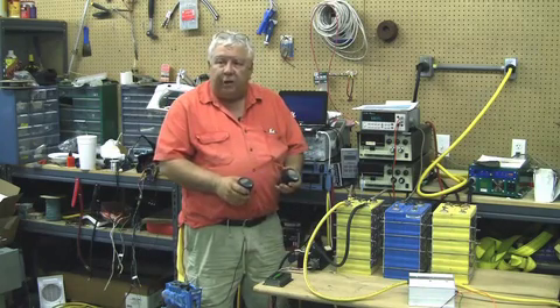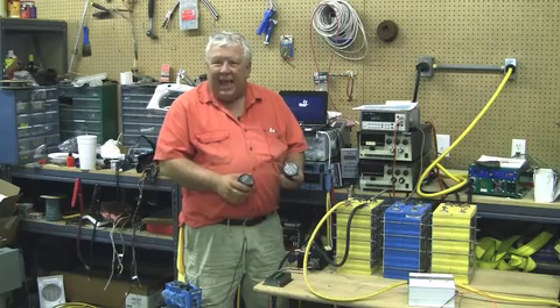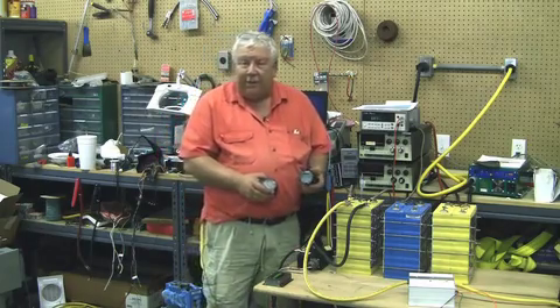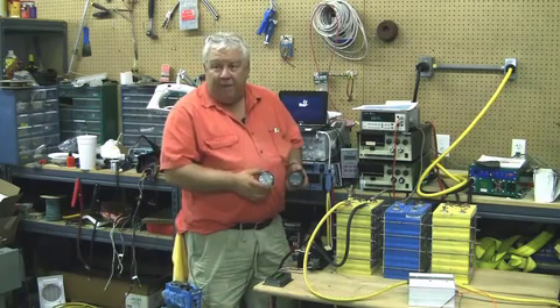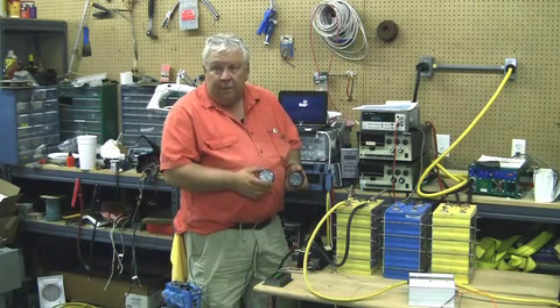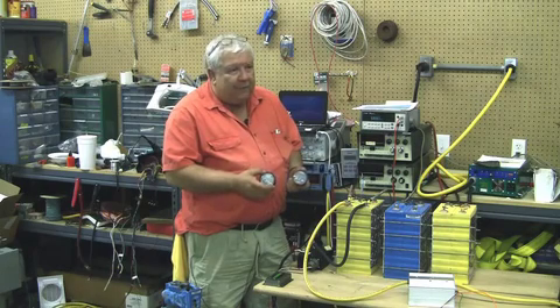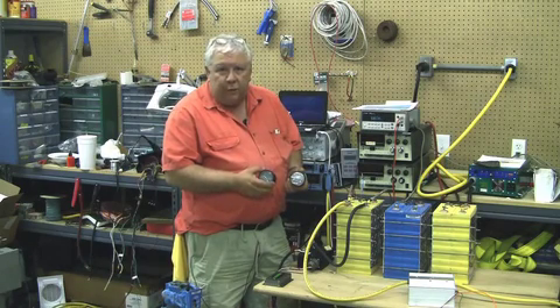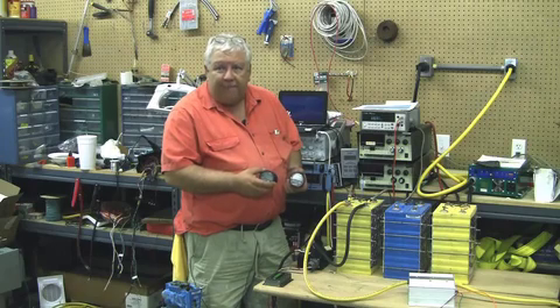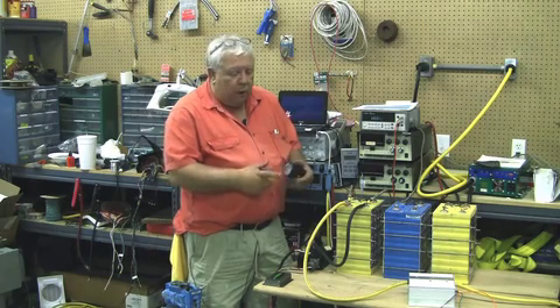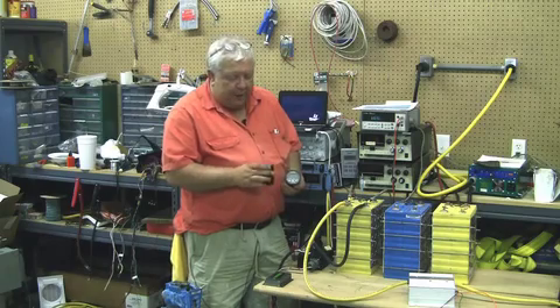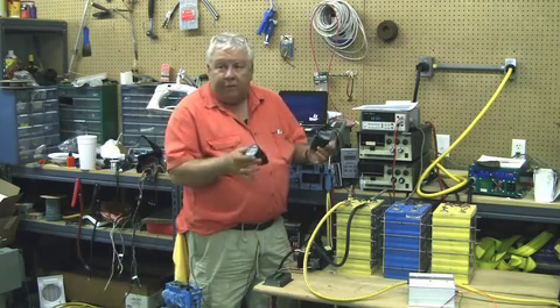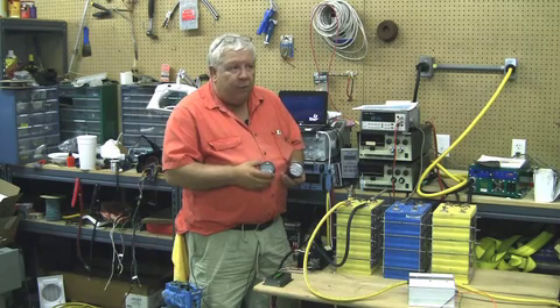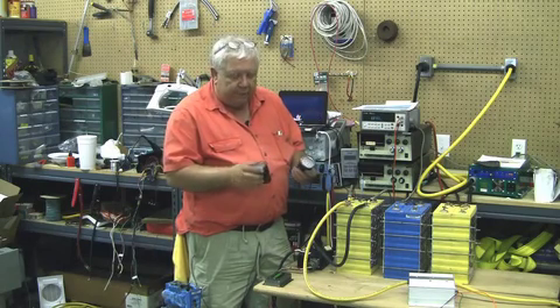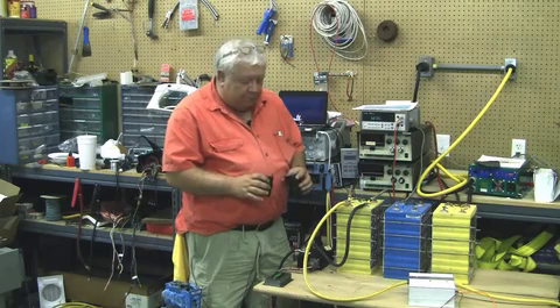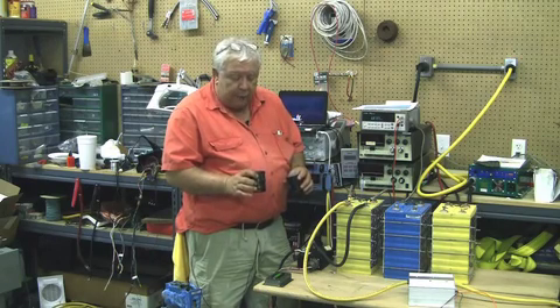They have a kind of cheap shunt, a 50 millivolt 500 amp shunt, and it doesn't look like it would hardly carry 500 amps. But understand, you can use any 50 millivolt 500 amp shunt. 50 millivolts is just the voltage reading you'd get across the shunt at 500 amps. You can get heavier, nicer shunts, you pay a little more, but they work with these just fine. A 50 millivolt 500 amp shunt is a 50 millivolt 500 amp shunt, though the heavier ones are often a little more accurate.